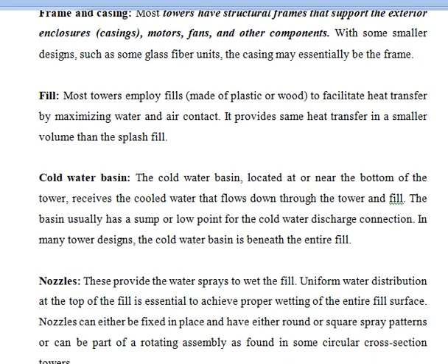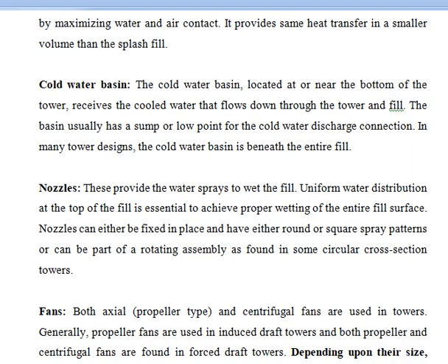Cold water basin: the cold water basin is located near the bottom of the tower. It receives the cold water that flows through the tower fill, and the basin usually has a sump or low point for the cold water discharge connection. In many tower designs, the cold water basin is beneath the entire fill. Again, the main thing is that you have to receive the cold water. The next is the nozzle.